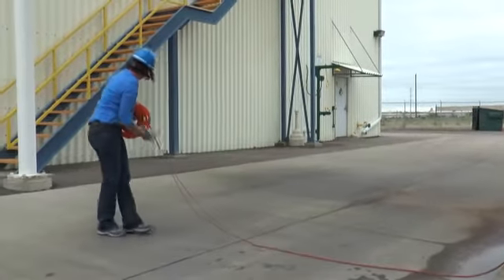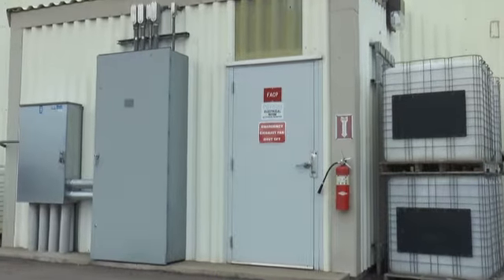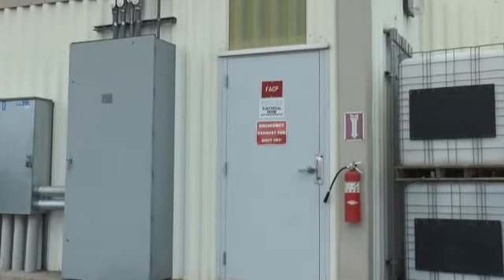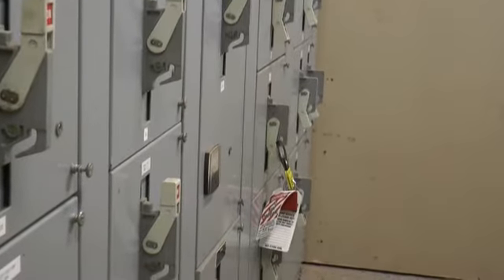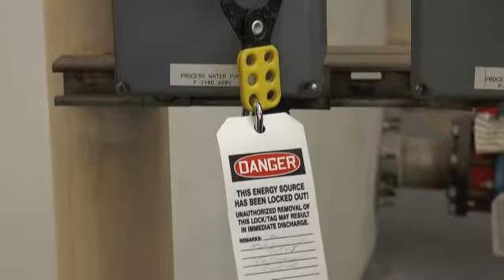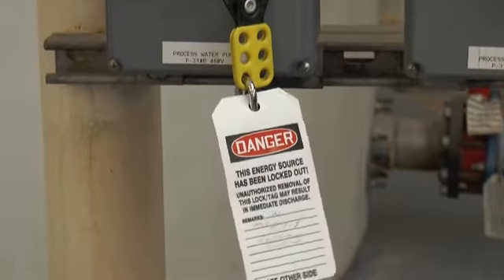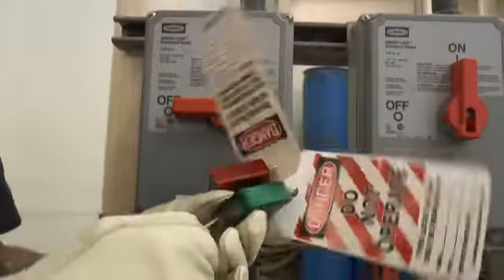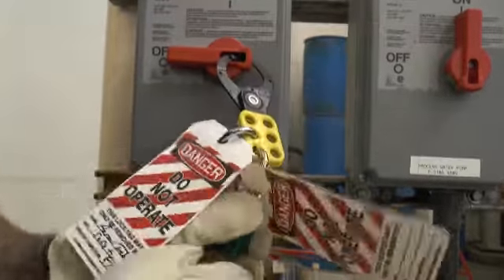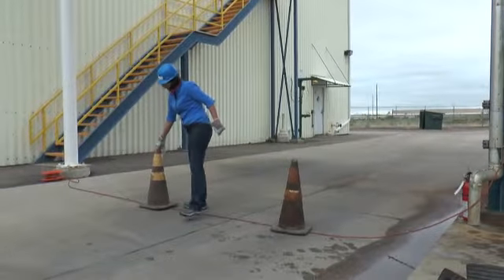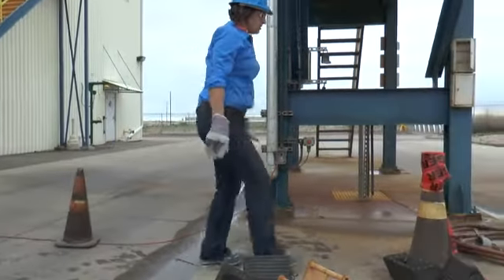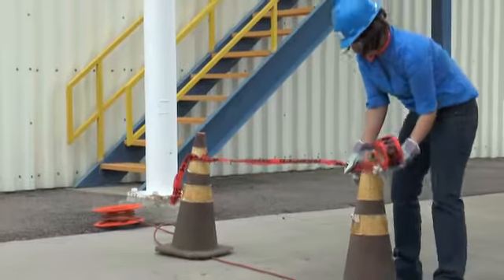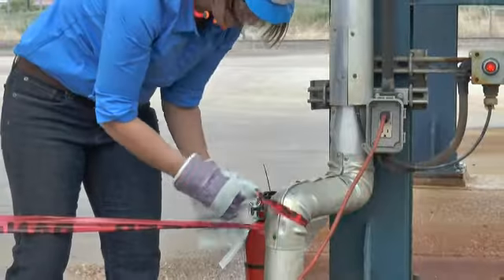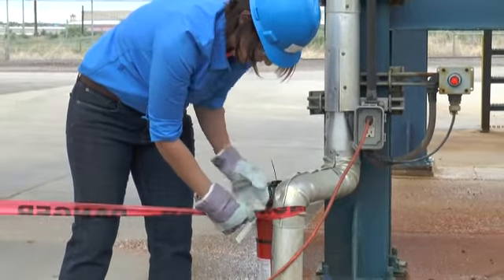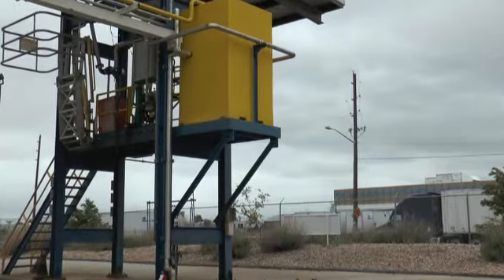All other workers must not enter or tamper with unauthorized electrical areas, including the MCC buildings or breaker panels. If possible, electrical energy sources shall be completely de-energized and verified as being in an electrically safe condition. Workers performing work on electrical systems must be involved in controlling the electrical energy using the facility's Lockout Tagout process and must verify that the system is de-energized before performing any work. GFCI ground fault circuit interrupters are required to be used on all outside electrical extension cords and tools, or if cords or tools are exposed to water or other liquids. Cords shall be protected against damage and shall not present a tripping hazard. A minimum distance of at least 10 feet shall be maintained at all times from overhead power lines.